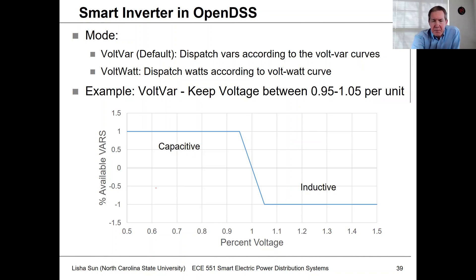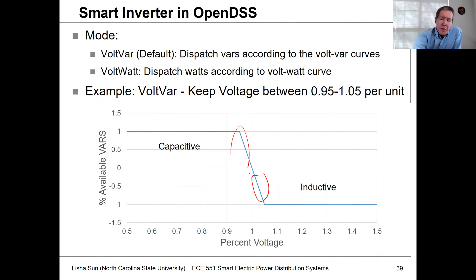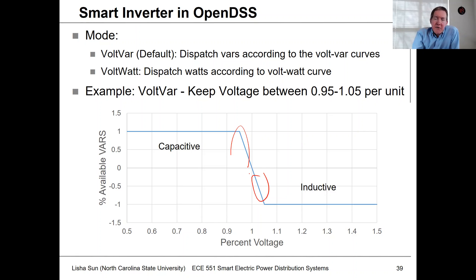In this application, if the voltage gets too low, we're going to push in reactive power. If the voltage gets too high, we're going to sink reactive power. So we're going back and forth between injection and absorption mode.